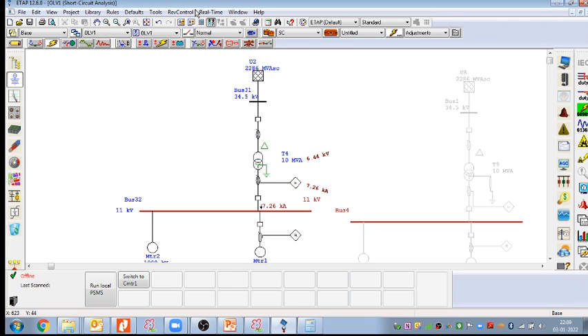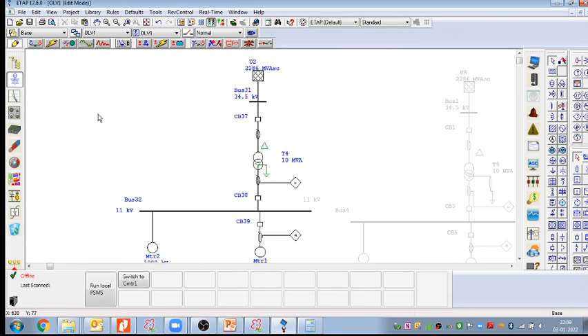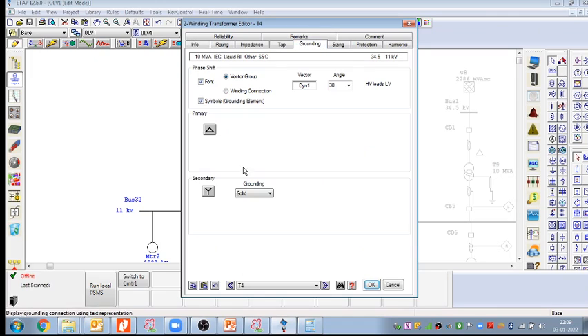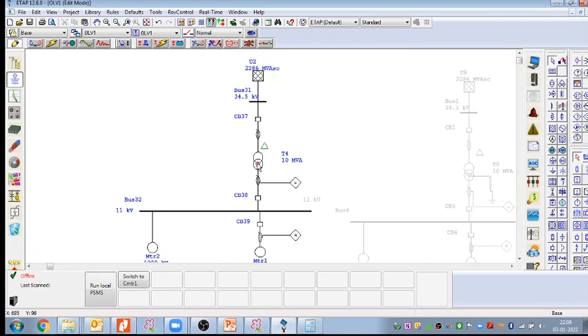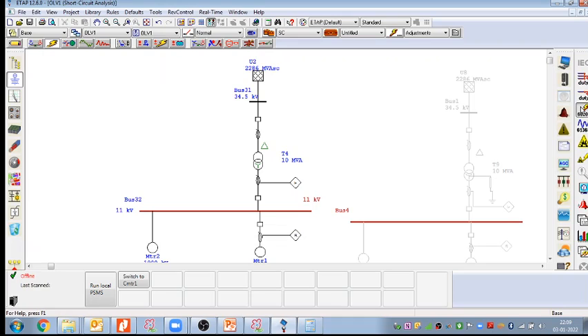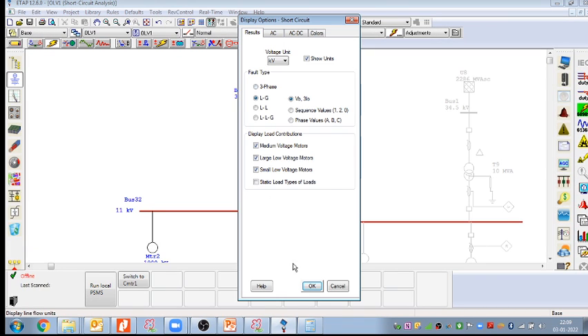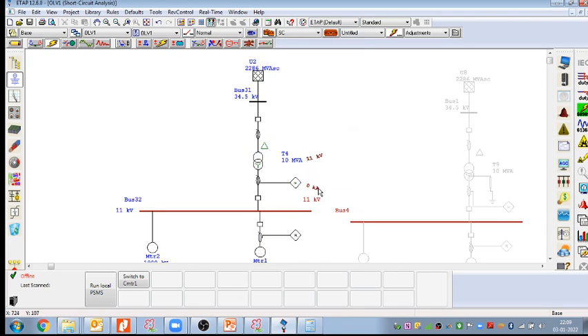Yeah, what is the confusion? Tell me. Repeat the statement. What kind of statement, Deepak? Sir, you told the ungrounded system and grounded system relation. You said one statement, so I just want to repeat it. The ungrounded means here you go and do the open, and now the system is ungrounded, right? And now if I run any line to ground fault, the system is ungrounded, so I cannot sense any fault current. It is coming 0 kiloampere.